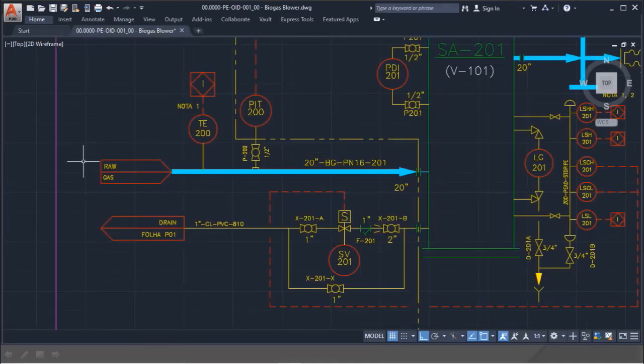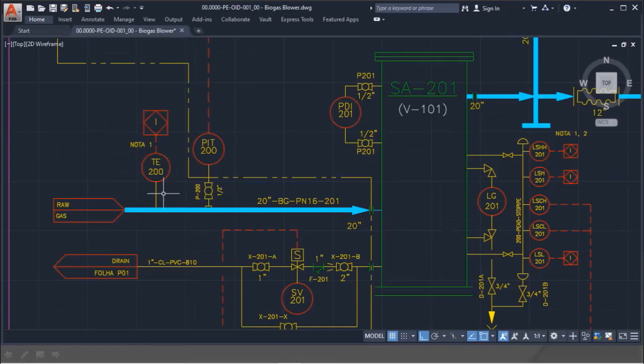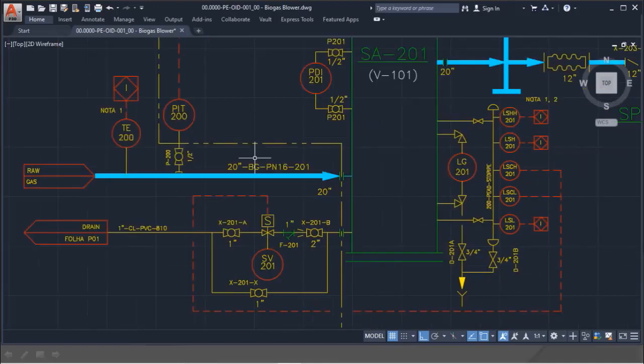This flag represents that the stream is going into the process. So we have the raw gas here, and we have a temperature element that measures the temperature of the fluid. We have a pressure indicator transmitter, and the pipe that feeds the plant is a 20 inch BGPN16201.